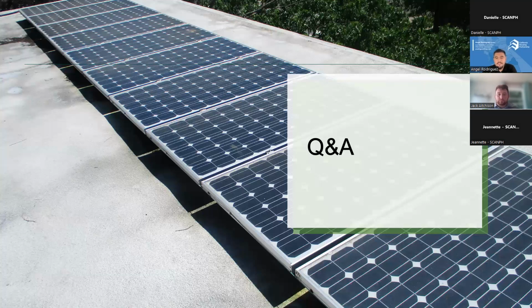So the last question we have mentions, new construction heat pump boiler water quality is questionable. How do you recommend approaching assessment for water softener needed or not needed? So what I would do is test the water, and you will get the grains of calcium bicarbonate and magnesium carbonate. You can refer to the manufacturer of the heat pump water heater that you're installing, and they will essentially say, do not install this with hard water that is of a certain grain level. And if you see that and you're in new construction, you may want to budget a water softener, or another option could be making sure that you have a pretty aggressive descaling maintenance plan.